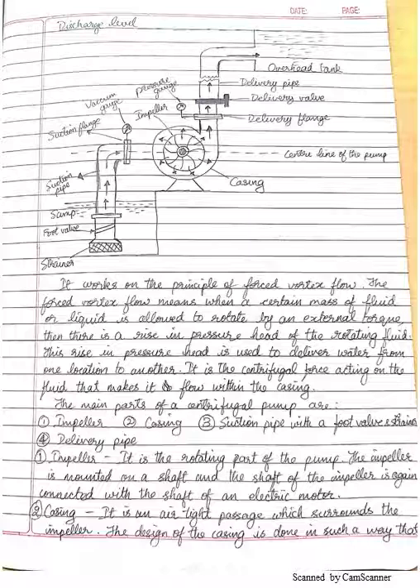The centrifugal pump diagram can be divided into three segments: the suction part towards the left and lower end, the impeller and casing as the central section, and the delivery side towards the upper end and tank. The working principle is based on forced vortex flow - when a mass of fluid is allowed to rotate by an external torque, the impeller rotates and causes a rise in pressure head of the rotating fluid, which is used to deliver water from one location to another.